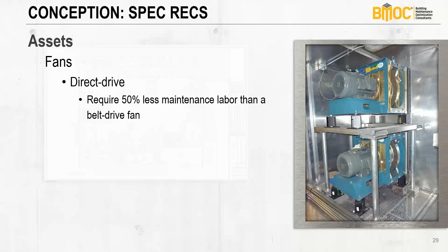So, 50% less labor than a belt drive fan, because the actual preventive maintenance steps are about half of what's required. Also, you only have to do PM on direct drive fans semi-annually, whereas for a belt drive fan it's recommended to be done quarterly.